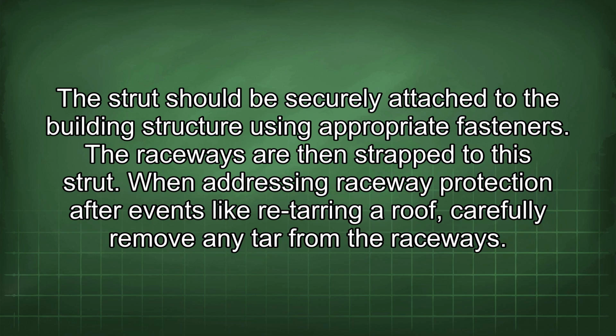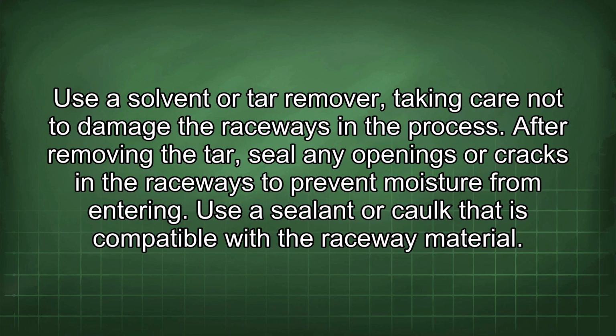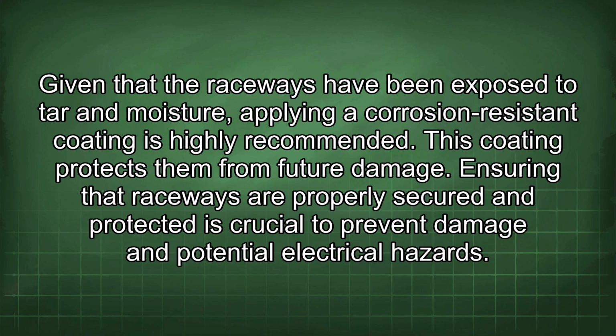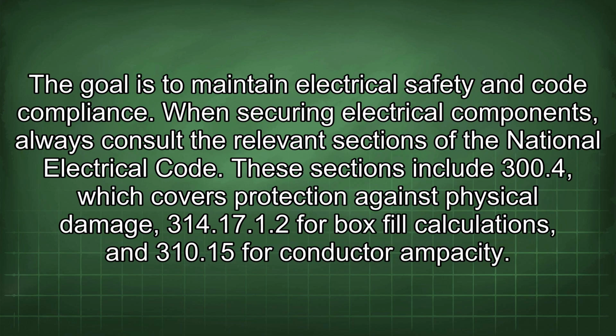When addressing raceway protection after events like re-tarring a roof, carefully remove any tar from the raceways. Use a solvent or tar remover, taking care not to damage the raceways in the process. After removing the tar, seal any openings or cracks in the raceways to prevent moisture from entering. Use a sealant or caulk that is compatible with the raceway material. Given that the raceways have been exposed to tar and moisture, applying a corrosion-resistant coating is highly recommended. This coating protects them from future damage. Ensuring that raceways are properly secured and protected is crucial to prevent damage and potential electrical hazards. The goal is to maintain electrical safety and code compliance.